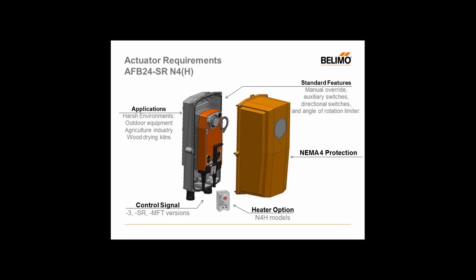Now the H at the end, if a heater option is required, the N4H comes with a heater built inside the housing with a thermostat already preset, which is adjustable as well for lower temperature operation and also condensation control. Now NEMA 4 is not offered on every single actuator, so you'll have to consult our catalog, and we also recommend contacting Belimo for further information on what kind of models and features are offered.